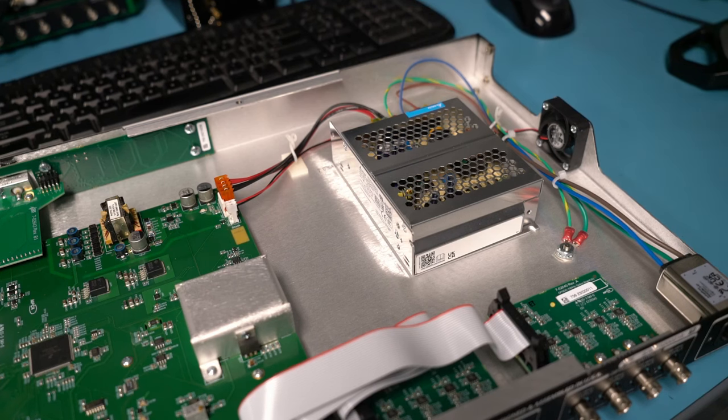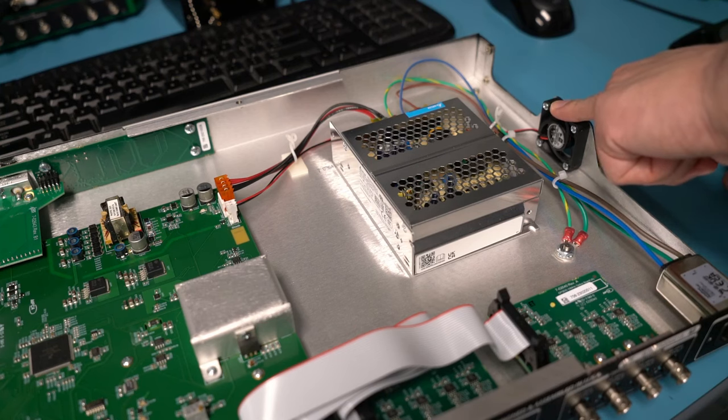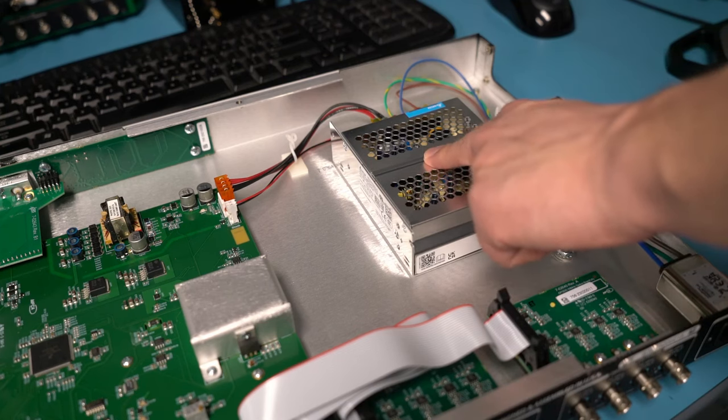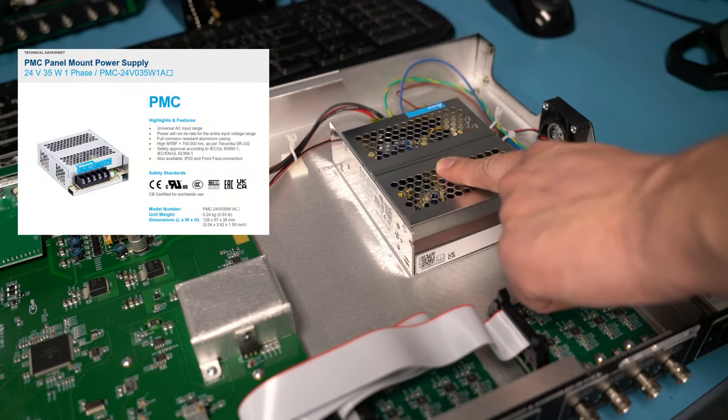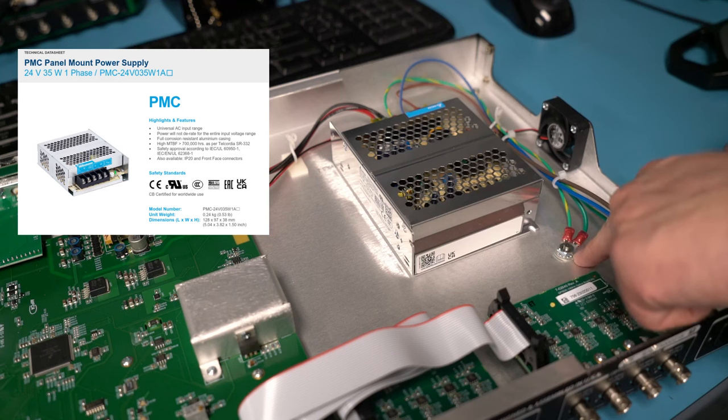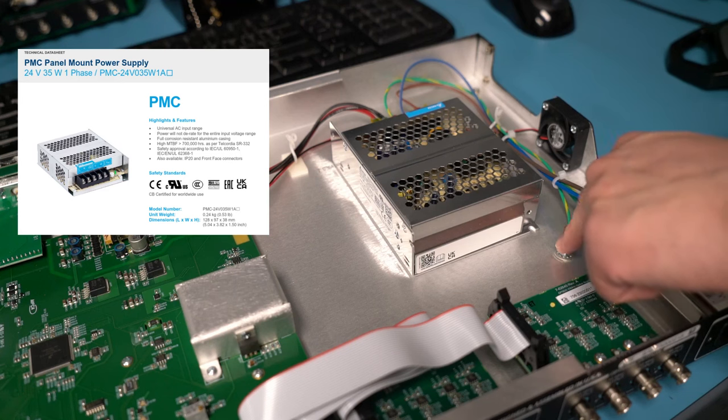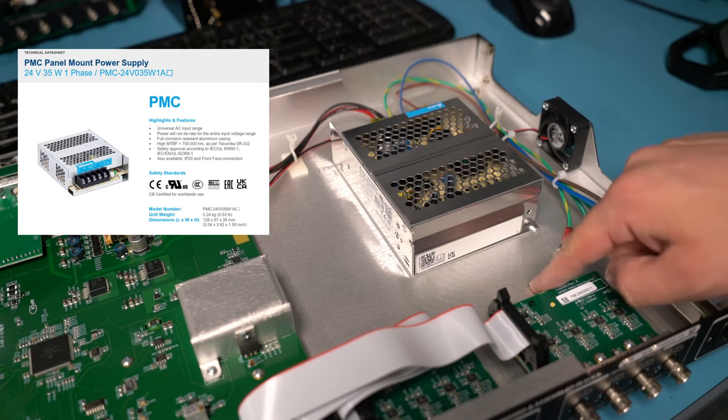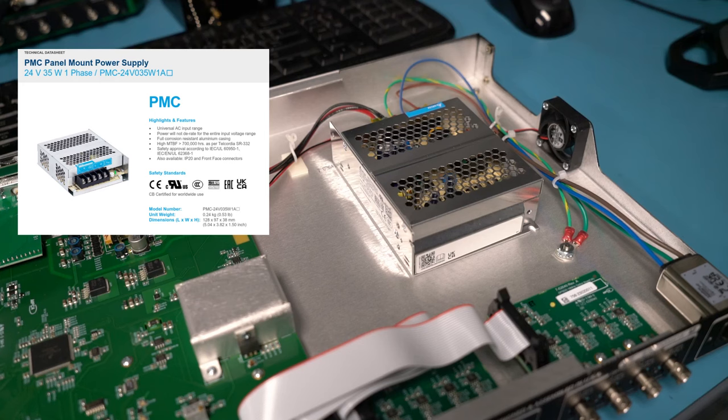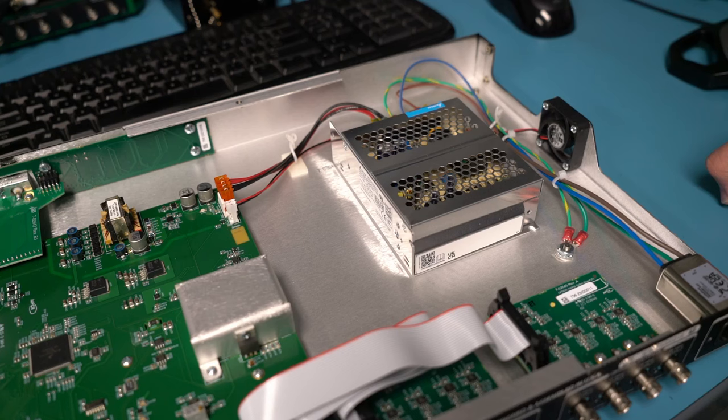Looking at the interior of the instrument from the rear there's a single cooling fan visible on the left side of the instrument which is primarily used for cooling the power supply. It's an off-the-shelf module from Delta that's nicely enclosed and shielded. We can see right here there's a grounding bolt that connects both to the power supply and to the mains inlet. There is a significant space between the power supply and the logic board and all of the analog components so we shouldn't have any concerns about noise from the mains input affecting the accuracy of the outputs.